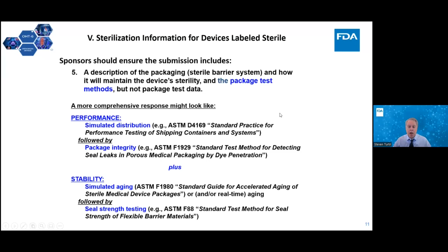It says all over it, example, and it's a hypothetical and it's draft because there are so many variances that can occur. There's so many different ways that you can test your packaging, but this is a common one that we've seen pretty frequently. I'm going to go through some of the finer detail of the text for you. In the intro, this represents a hypothetical series of simulations and subsequent tests intended to provide a high level of assurance that the packaging will demonstrate adequate stability and the packaged product will be able to withstand real-world worst-case shipping and handling without package failure or sterile barrier breach. The details of this test schedule may or may not be appropriate for other products, as test procedures should be developed on a case-by-case basis.